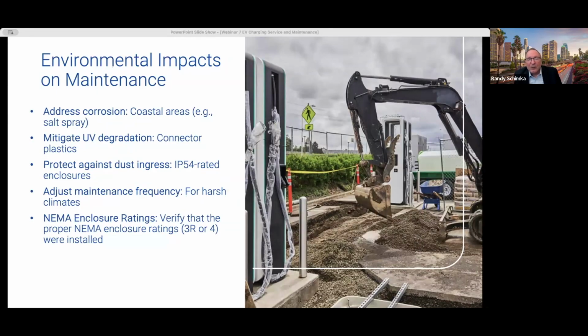First is the issue of addressing corrosion in coastal areas. Salt spray can corrode metal components, so inspect enclosures and connectors regularly. Stainless steel enclosures are the most resistant to this type of corrosion. Next, we want to mitigate UV degradation. Sun exposure can make EV charger connector plastic brittle over time. Check for cracks or fading and replace any affected parts to maintain reliable connections.